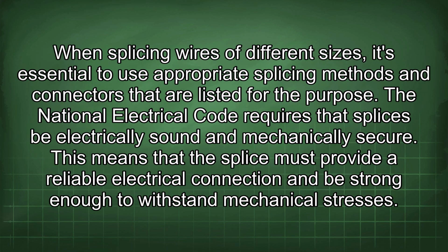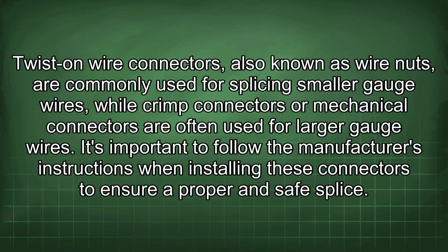When splicing wires of different sizes, it's essential to use appropriate splicing methods and connectors that are listed for the purpose. The National Electrical Code requires that splices be electrically sound and mechanically secure. This means that the splice must provide a reliable electrical connection and be strong enough to withstand mechanical stresses. Twist-on wire connectors, also known as wire nuts, are commonly used for splicing smaller gauge wires, while crimp connectors or mechanical connectors are often used for larger gauge wires. It's important to follow the manufacturer's instructions when installing these connectors to ensure a proper and safe splice.